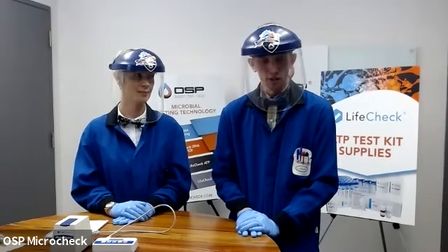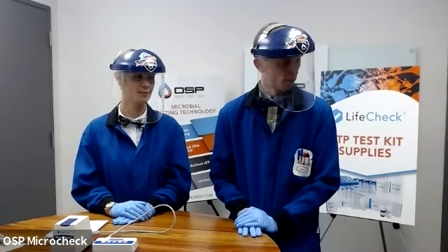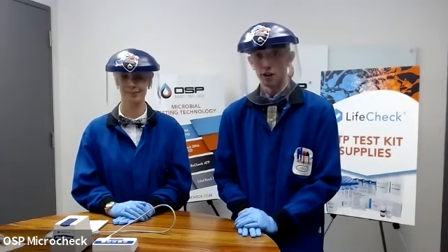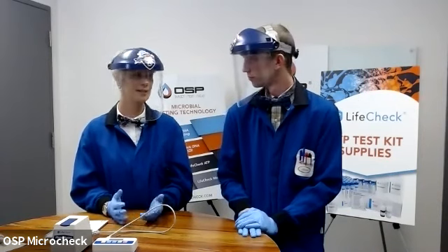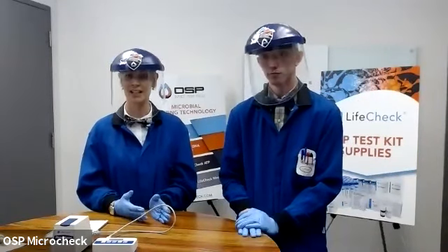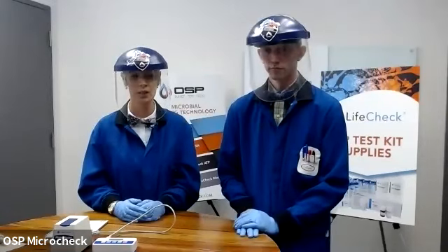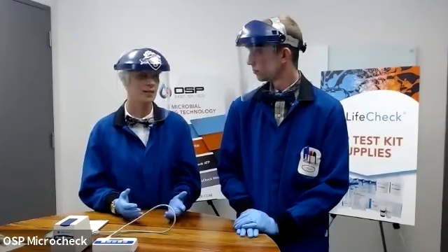If you have any concerns around biocides, I do have a couple slides I can share with people that showcase what is affected, or more importantly, what is not affected. Because in most cases, the addition of biocides isn't that detrimental at all to the measurement of ATP. And the nice thing about oxidizers is that they react quickly and they're gone. It typically happens only when you're dosing at really high concentrations, which in most of our applications we don't. So if you're dosing at demand and you give it enough time that it gets completely consumed, there should be no interferences. But depending on how you're conducting this type of testing and what you're trying to get out of it, we can provide some guidance on that.